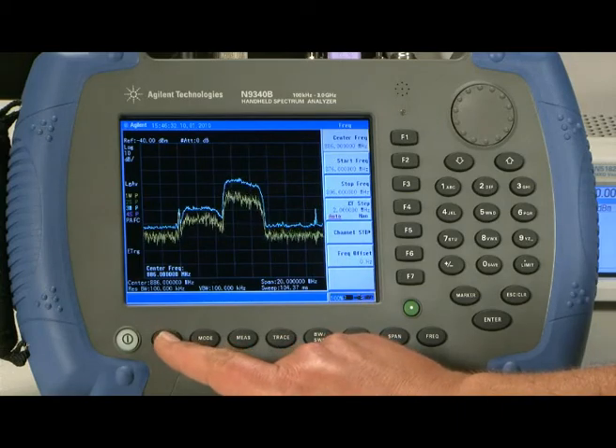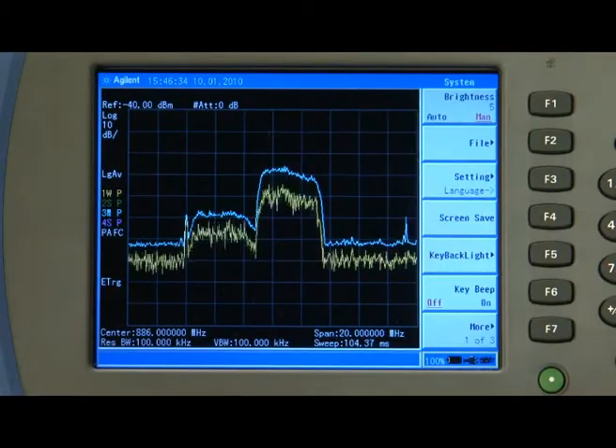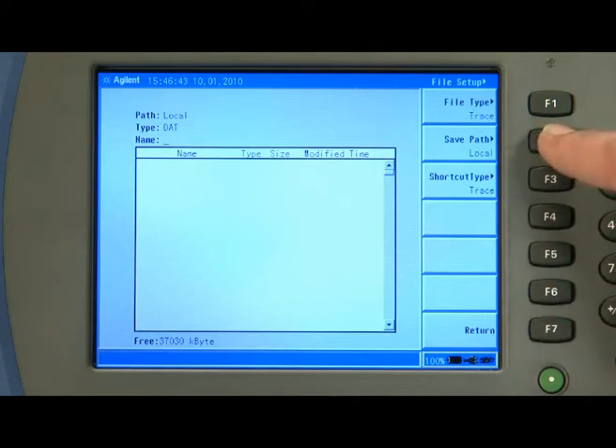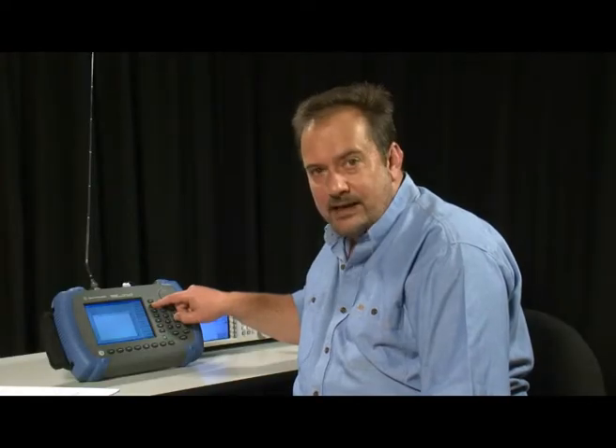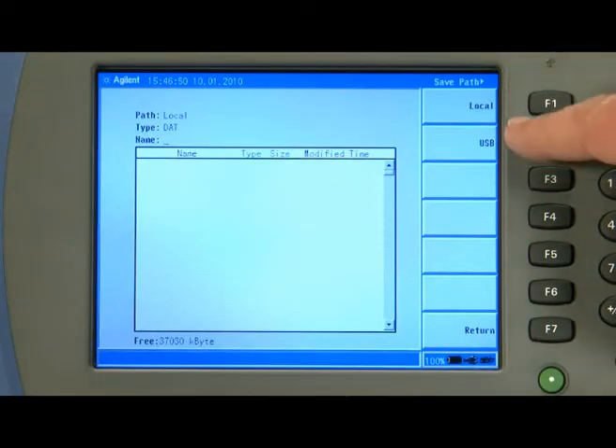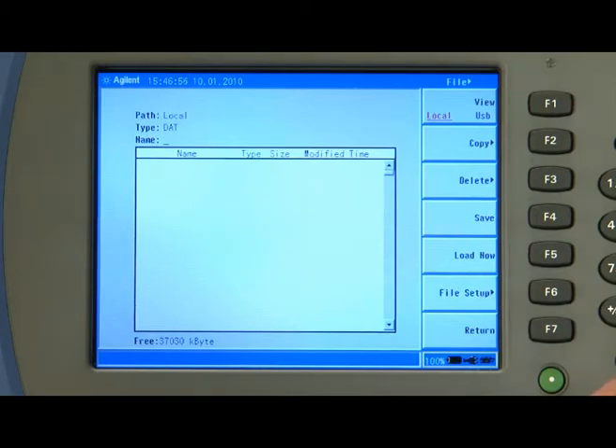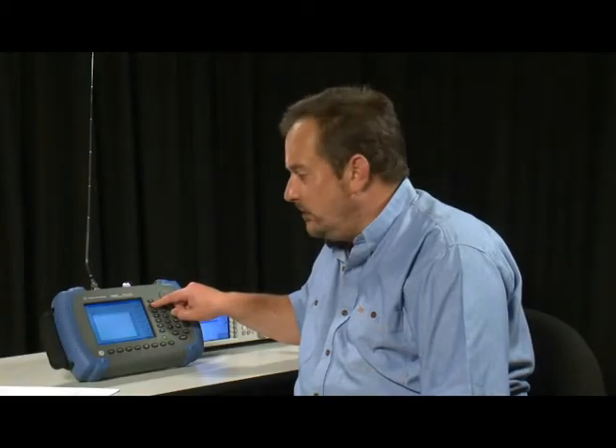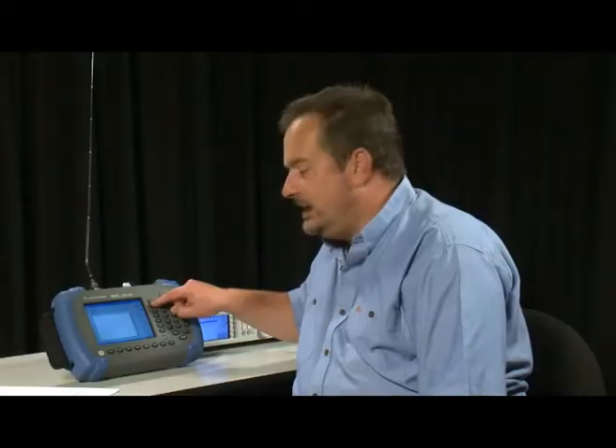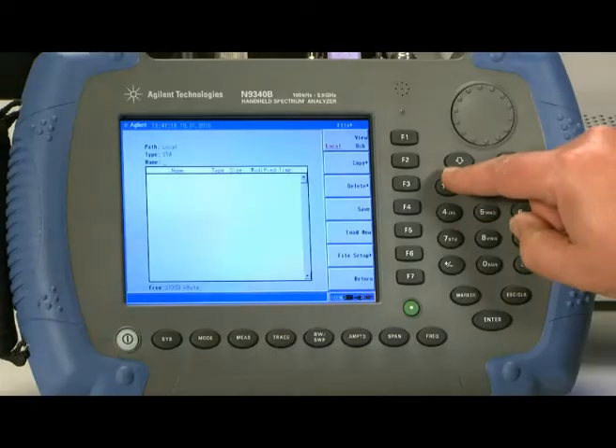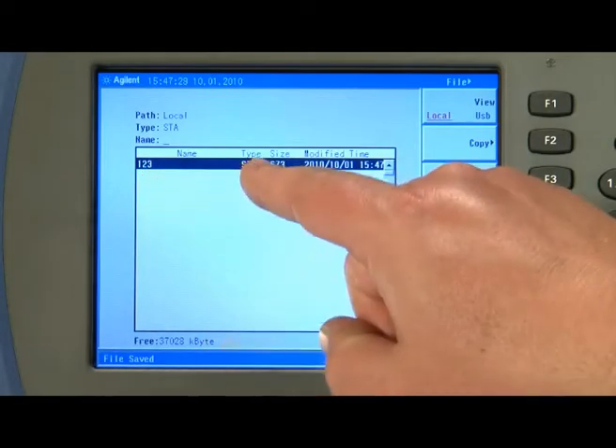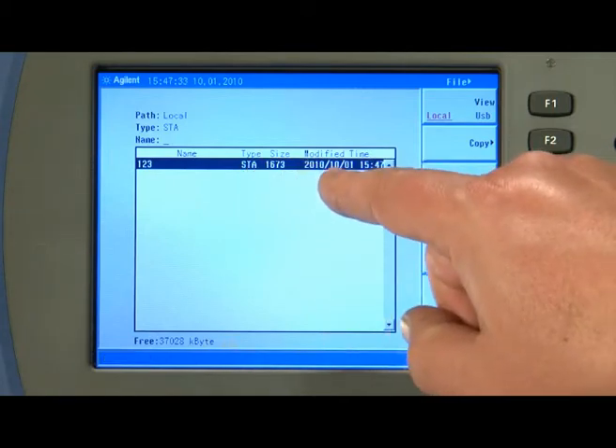So let's call up the file save menu by pressing the system button and then we are going to select the internal memory so I am going to press file and then file setup and the save path is currently set to local which is what I want. But if I wanted to store to the USB memory stick I could change that to USB but we will leave that as local for now. Then we are going to select the file type so we press file setup and the kind of file we want to save here is an instrument state so that I can recall it later if I wish to. So I will press the state button. Then we can enter a file name using the numeric keypad. So I will call this 123 and then I will press save and that state has now been saved into the internal memory. You can see that here the file name is 123 it is a state file and it was saved on the 1st of October 2010.